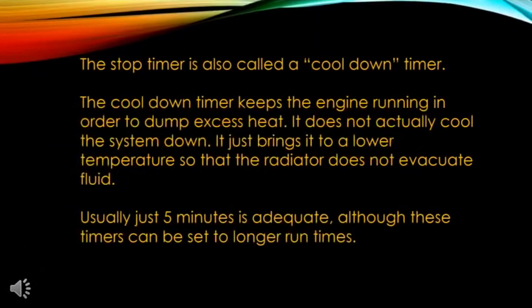The stop timer is also called the cool-down timer. It keeps the engine running in order to dump excess heat — it does not actually cool the system down, it just brings it to a lower temperature so that the radiator does not evacuate fluid. Usually just five minutes is adequate, although these timers can be set to longer run times.